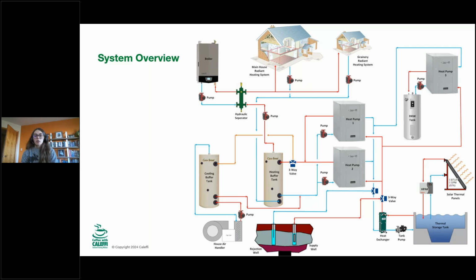The groundwater temperature in Bozeman is about 47 degrees Fahrenheit year round. Anytime the thermal storage tank is hotter than the ground—greater than 47 degrees—the system pulls heat from the thermal storage tank. Anytime the tank gets depleted below 47 degrees, the 3-way valves switch and pull water from the open loop ground source heat pump instead.